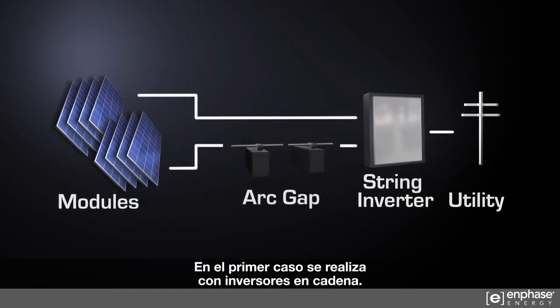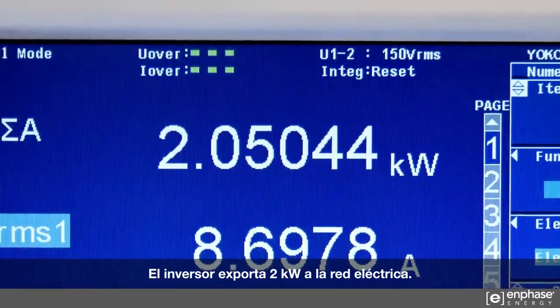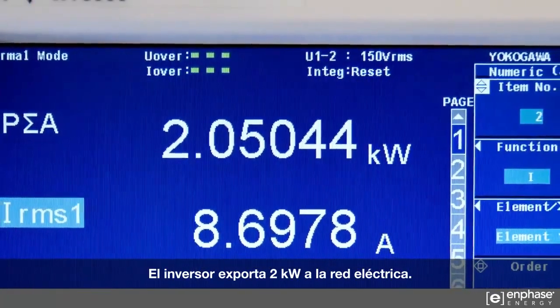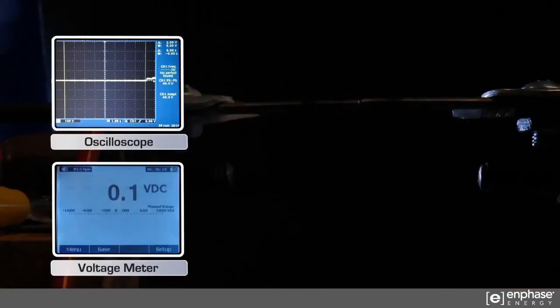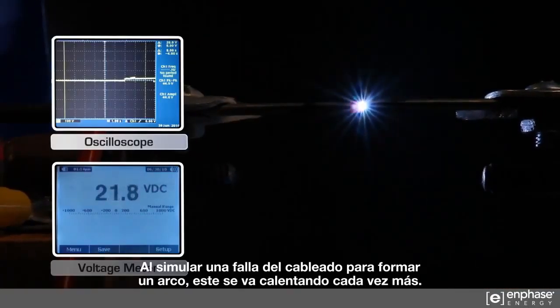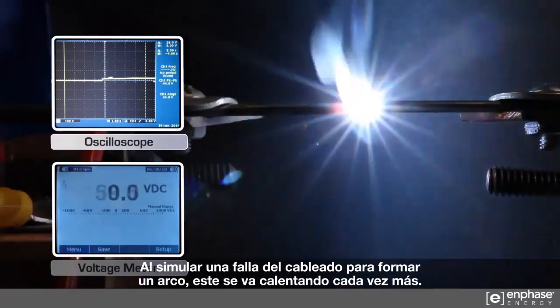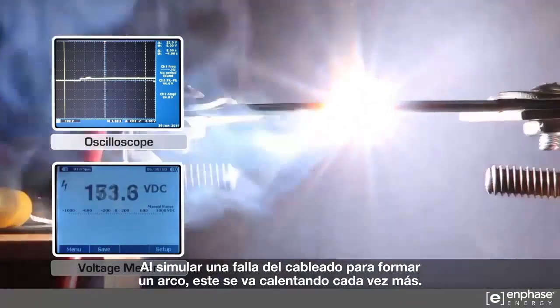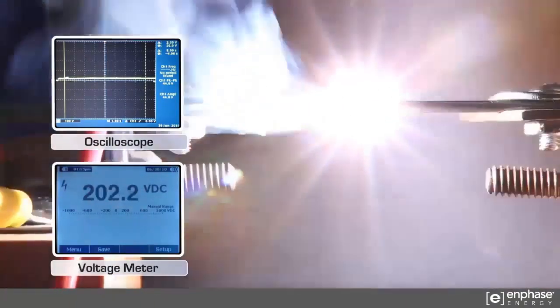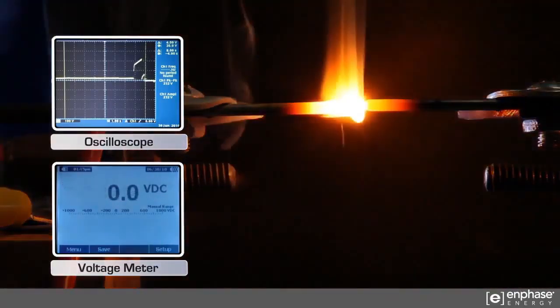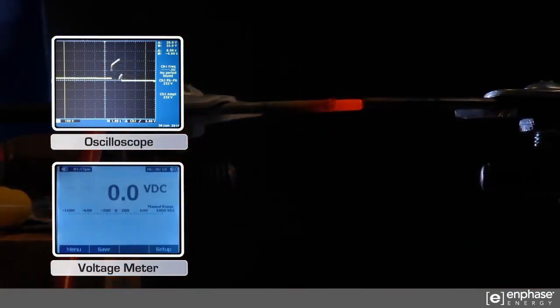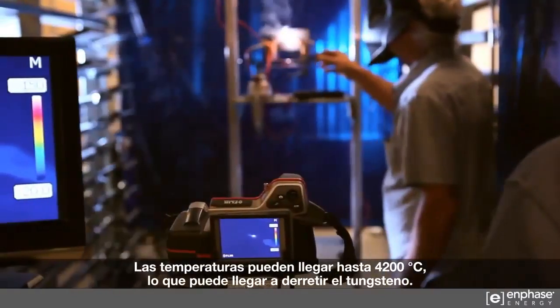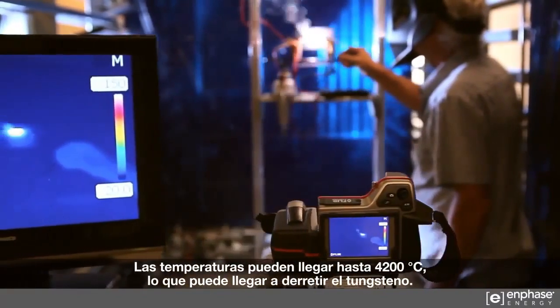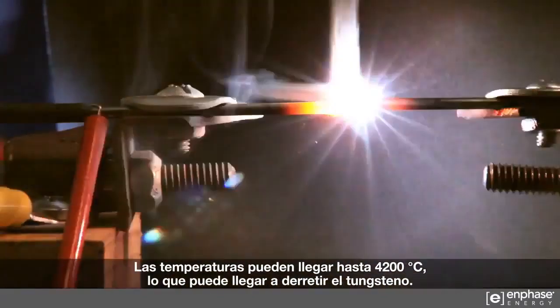The first case simulates a string inverter scenario. The inverter is exporting 2 kilowatts to the grid. As we establish an arc by simulating a wiring fault, the arc gets hotter and hotter. Temperatures can reach up to 4,200 degrees centigrade. This is hot enough to melt tungsten.